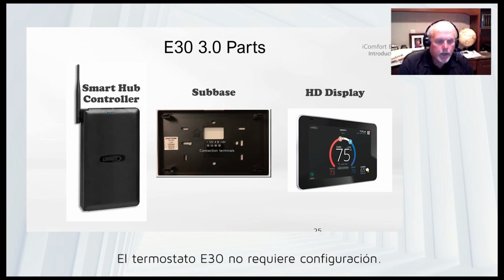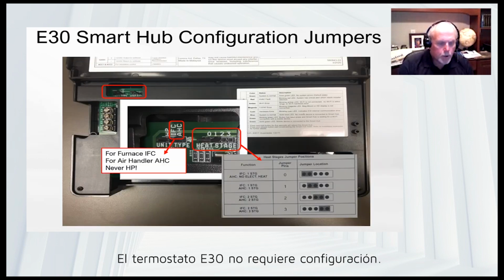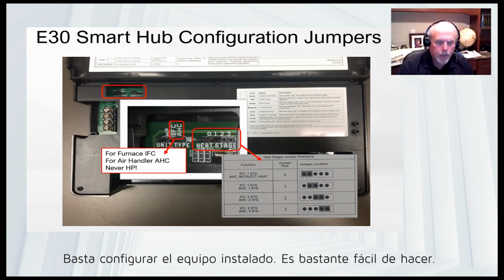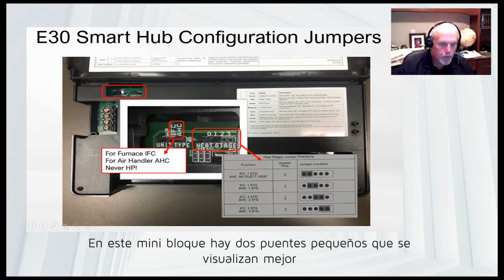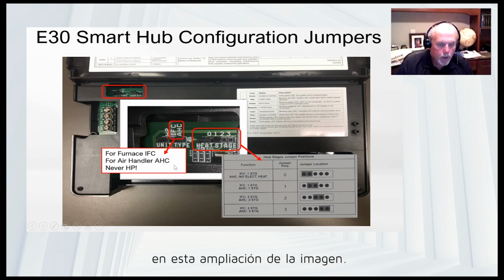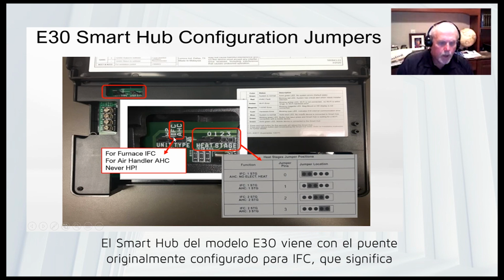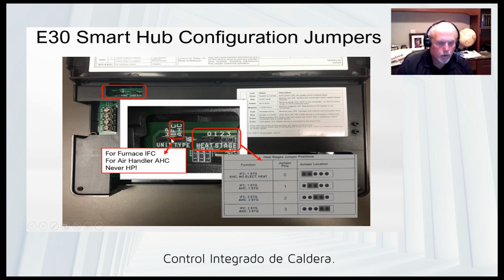equipment. Since the E30 does not communicate directly with the equipment, you do have to set it up. Okay, you do have to configure the type of equipment that you have. Okay, so it's pretty easy to do. This excerpt here is these little two jumpers up here. It's a little small, so I had to blow it up and I put it here. Okay. So the E30 Smart Hub comes with the jumper defaulted to IFC. So from the factory, it will be on IFC, which stands for Integrated Furnace Control.